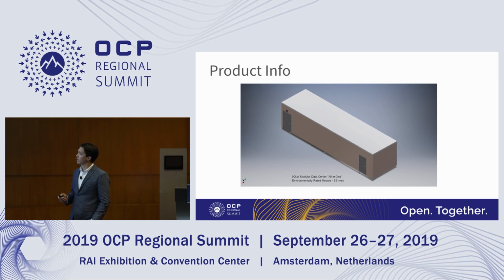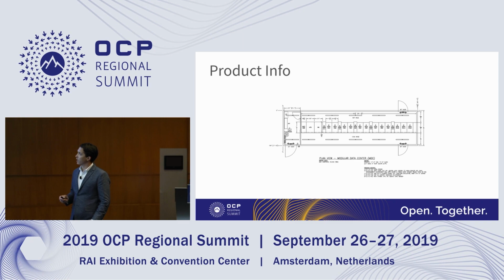There's the cladding. And there's the layout. You have an isolated area. Feedback was, how do we make this look and feel as much like a traditional data center? Because our operators don't want to walk into an environment that they're not familiar with or can't be safe in. So the exits, this is based mostly on an American US deployment. So we have egress and the National Electric Code that dictates the distances of this. You'll notice a fairly large hot aisle, which may not be necessary with 100% OCP gear. Right now we're pushing the limits and pioneering what we can get away with with all authorities having jurisdiction and inspectors.